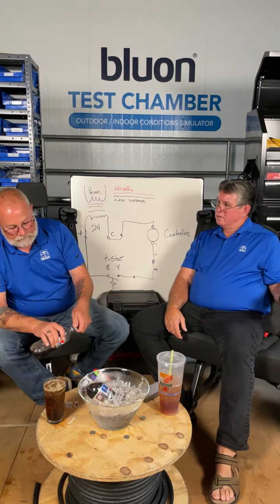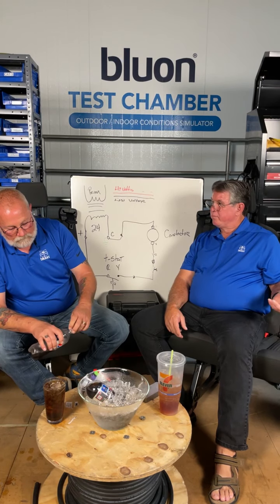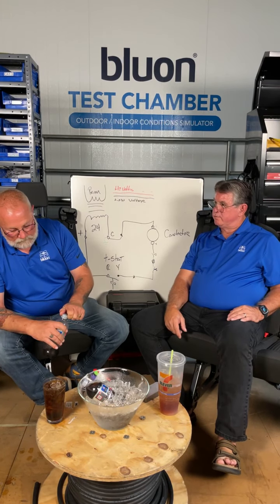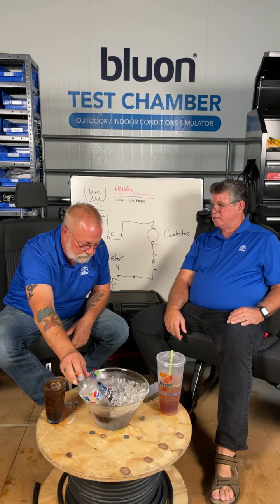Yeah. Some operating controls. I had one the other day where the guy was short of wire, and it was in a hospital. So you leave the fan on all the time, and stage your first stage and second stage cooling until you get the other wires pulled. So you can make some trade-offs, because in a hospital environment, it's not going to hurt you to run the fan continually. But you never want to jump out safeties other than for testing. A real quick test. Testing purposes only. Yeah. Do not walk away.